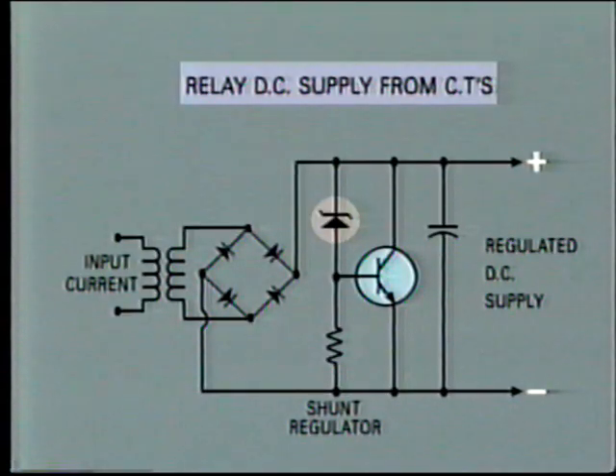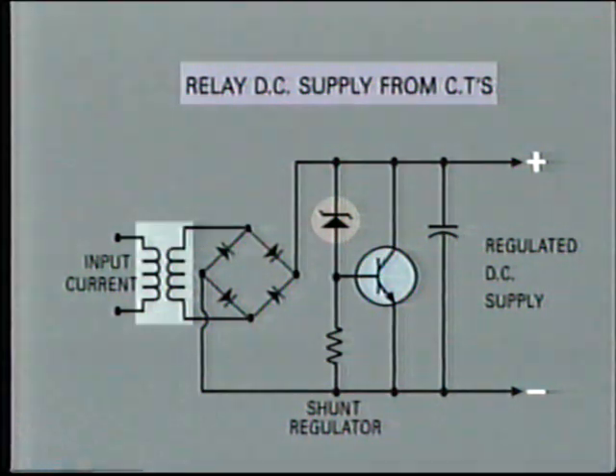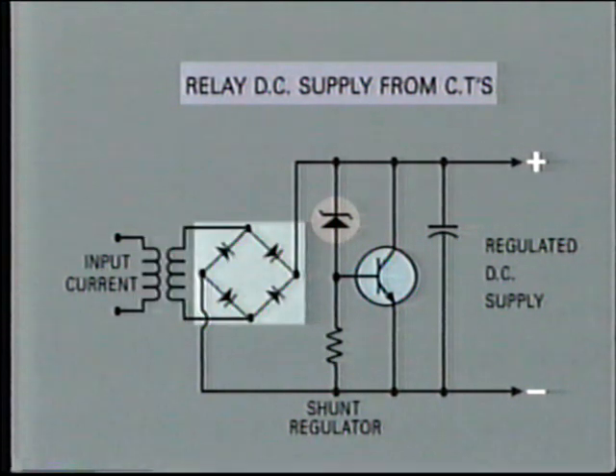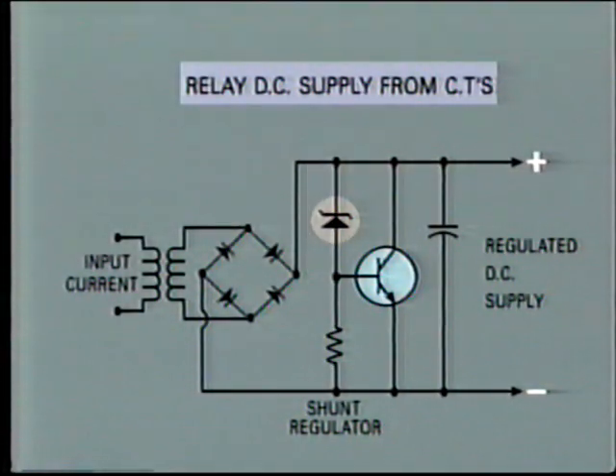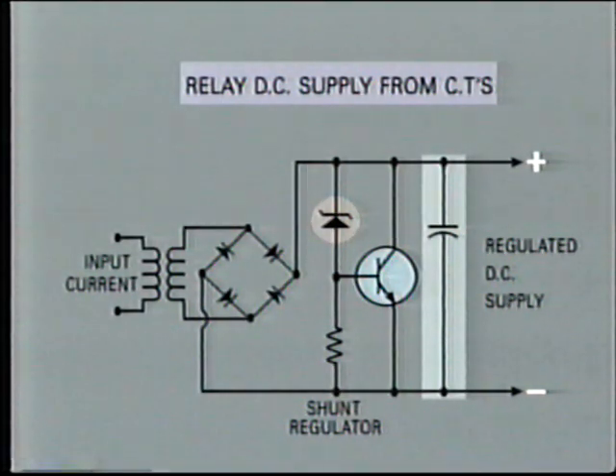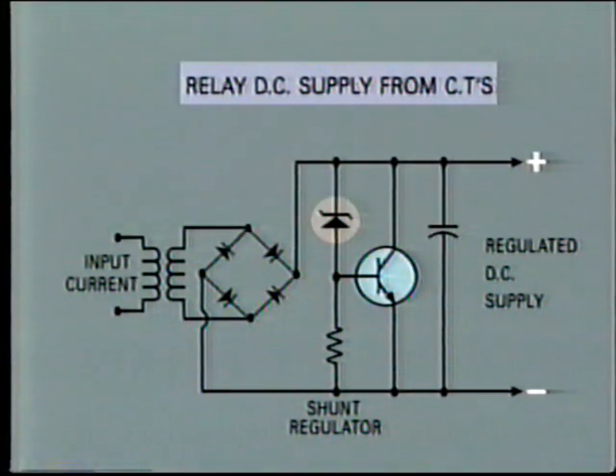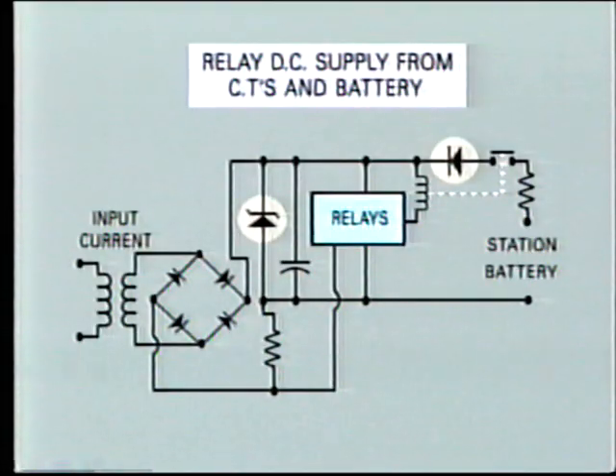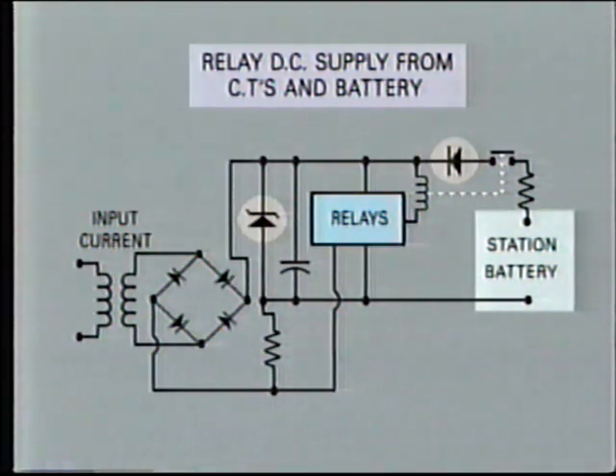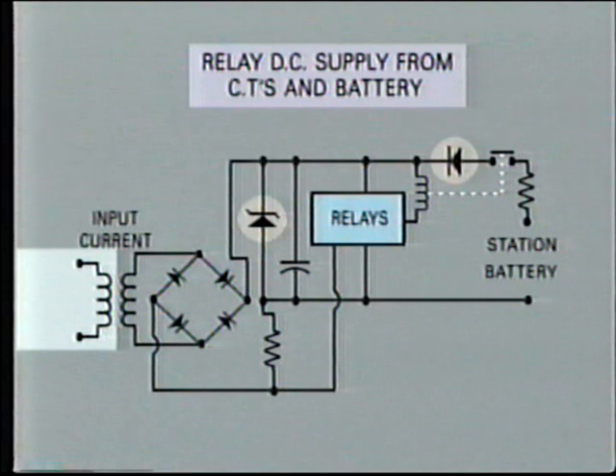Another method of providing power to the relay is by using the input current from its own CT or VT. Here, the input signal is transformed to an appropriate voltage, rectified, and regulated. Once again, a capacitor is installed to absorb transients. A disadvantage of this power supply arrangement is that it increases the burden on the CTs. In some relays, power supply is by a combination, that is, from the station battery and/or the measuring circuit CTs or VTs.